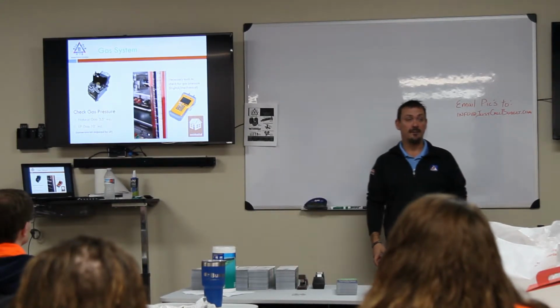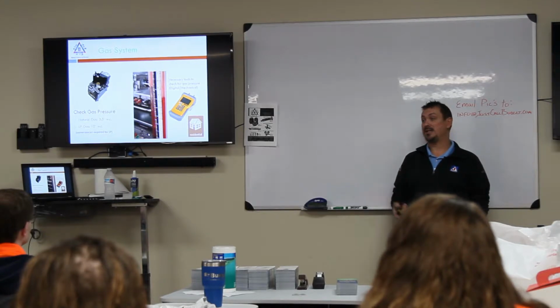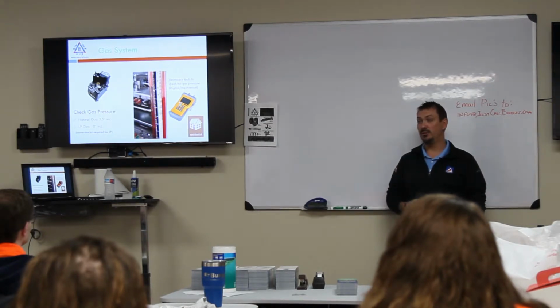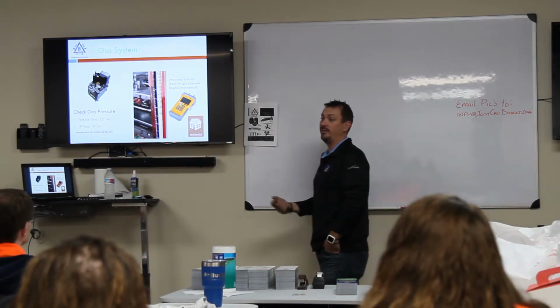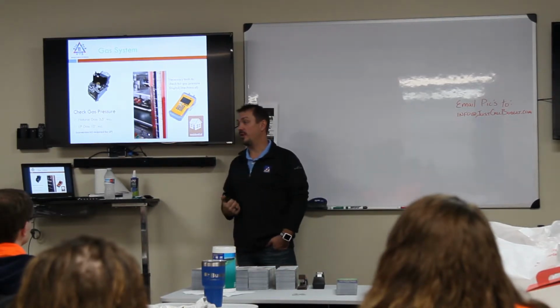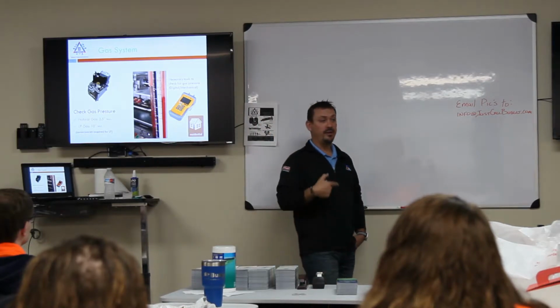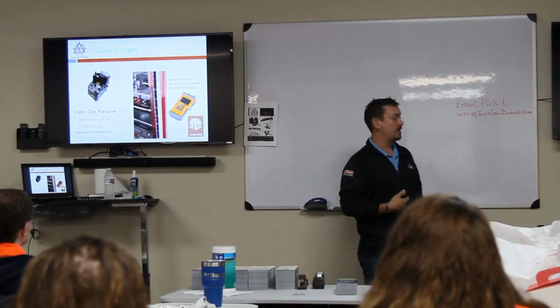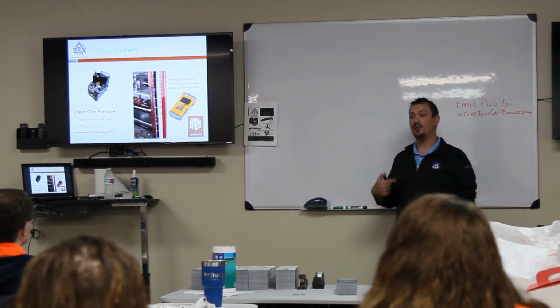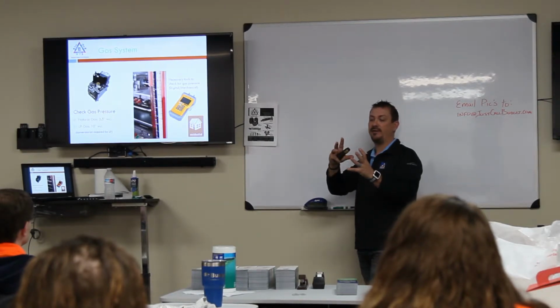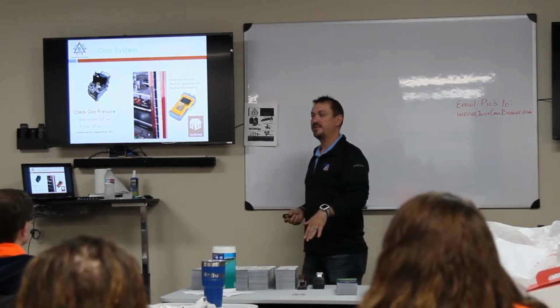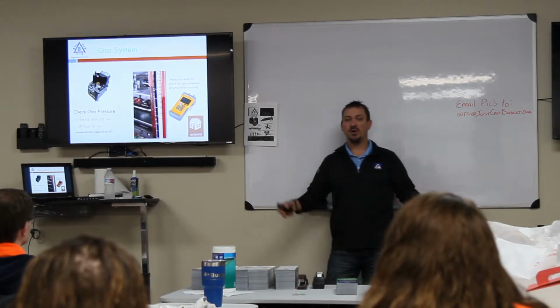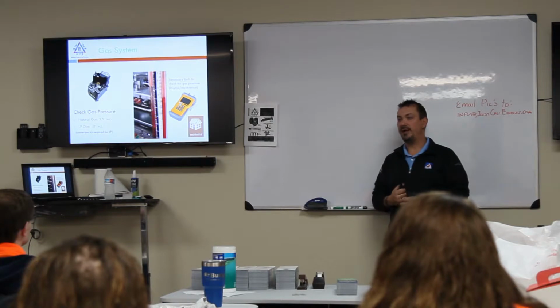So we checked the gas pressure. His gas pressure was really low. We increased the gas pressure back up to 3.5, and all of a sudden we've got the efficiency back to 80% on that equipment. So every year you need to check that gas pressure. Any gas valve that you install, I don't care if it's in a box this big, or if it's in a box that's 33 inches tall and 17 inches wide and has a furnace wrapped around it, 34% of every gas valve that gets installed is not calibrated properly.